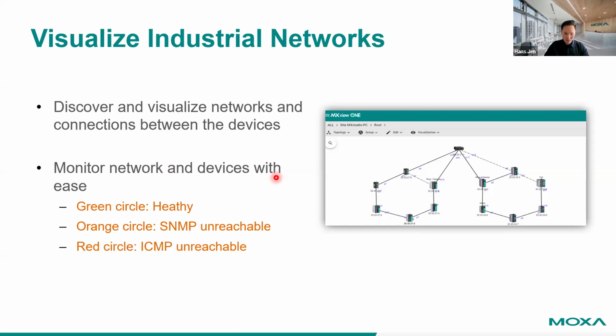Imagine you have installed thousands of devices on site during commissioning. How do you know the PLC in the first container is connected to which port on which switch? Also, if you have redundancy protocols running in your network, such as RSTP, STP, turbo ring, and turbo chain, MXview uses solid lines to indicate forwarding ports and dotted lines for blocking ports, so you can monitor your traffic flow better.